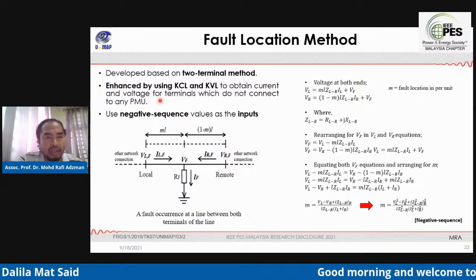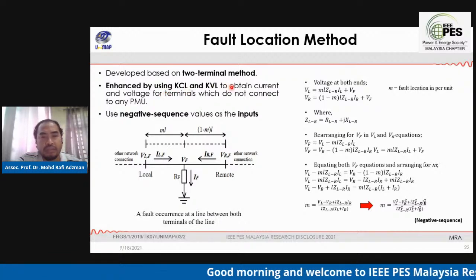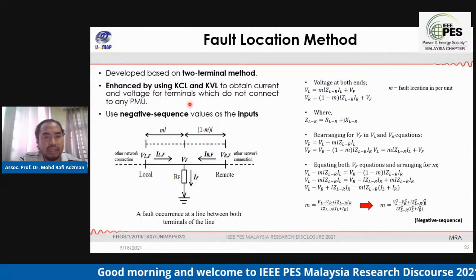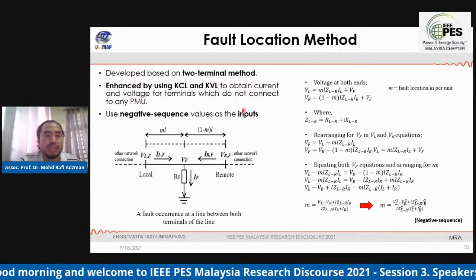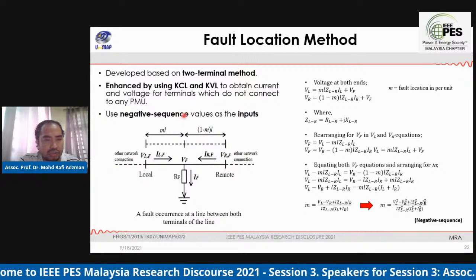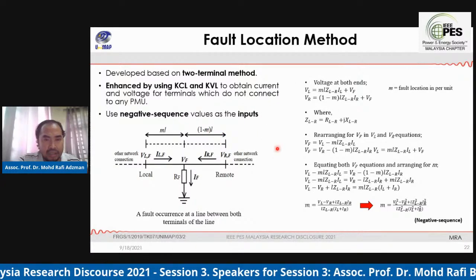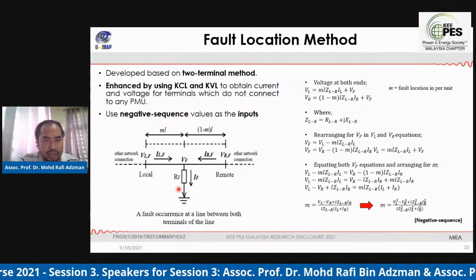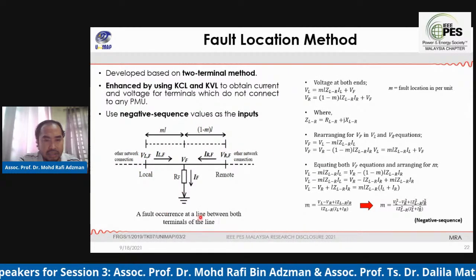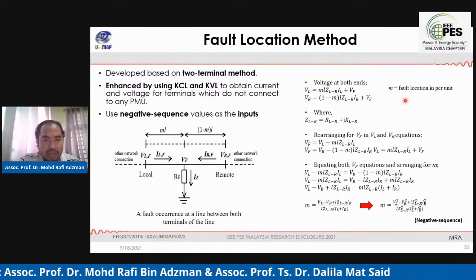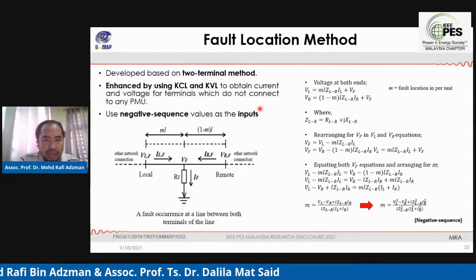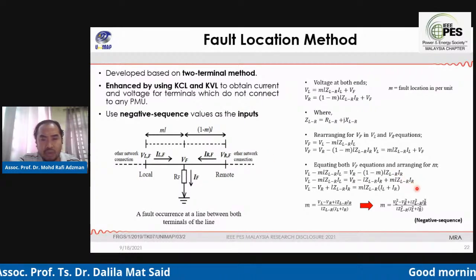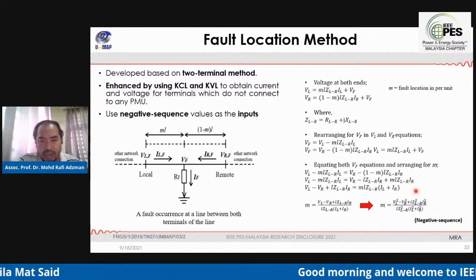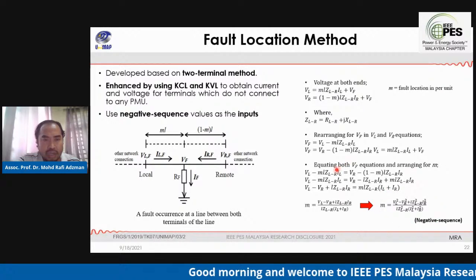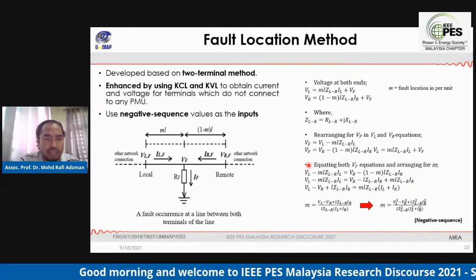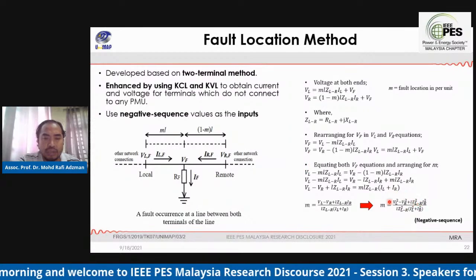The fault location method we developed is based on the two-terminal method. It is enhanced by using KCL and KVL to obtain the current and voltage for terminals which do not have any PMU. In this algorithm, we use negative sequence values as the inputs. Based on these figures, we can develop the algorithm and implement it with negative sequence values. This is the formula that we use to estimate the fault distance using negative sequence values.